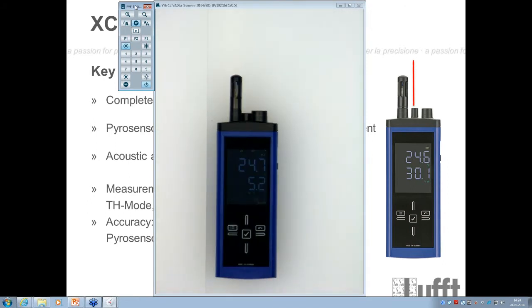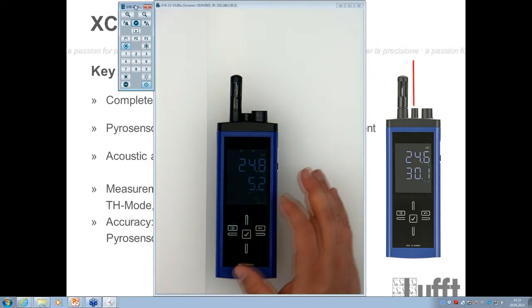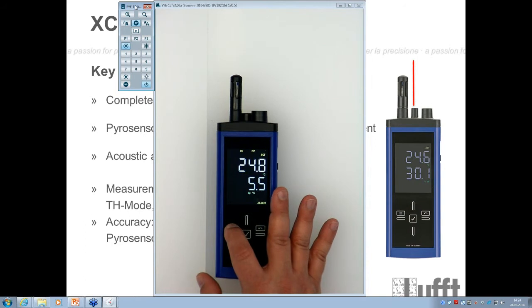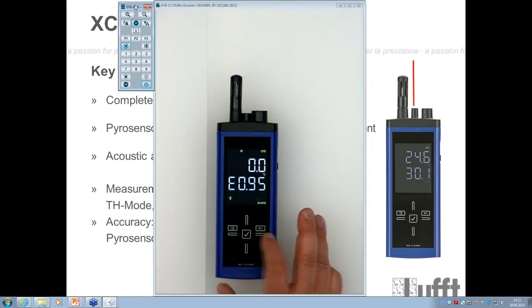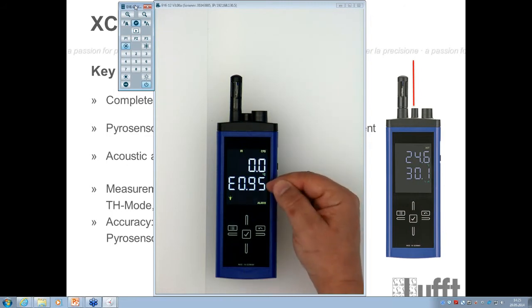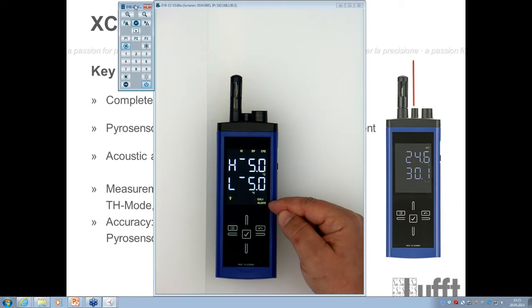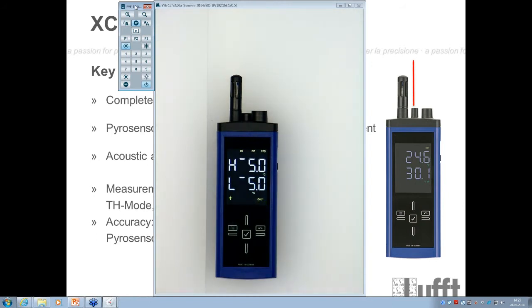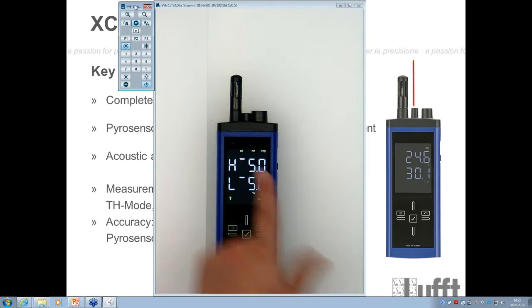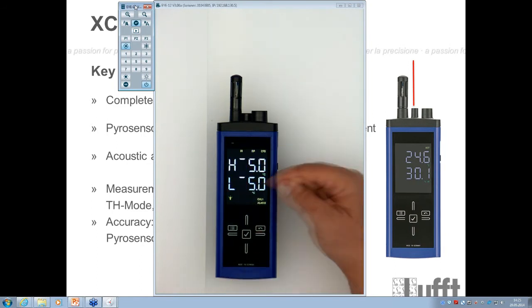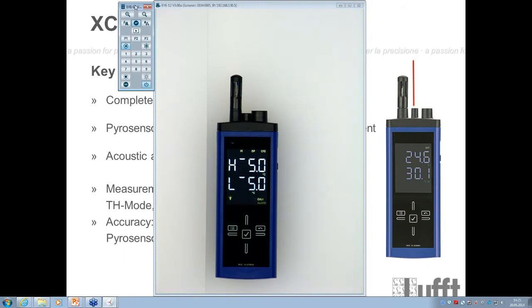If you want to change here now, of course I told you before that you have two thresholds, a high and a low threshold for the dew point to enter the alarm. Then you have to enter it into the configuration menu. You go to Cal 1, temperature offset, and emissivity value again, and the next step is, and now the alarm is blinking, that's the configuration menu for the alarm. It's a high threshold and a low threshold, which is configured for 5 degrees. Again, I will go back and show you. 5 degrees, 5 degrees. What does that mean? That means the alarm threshold is the sum of the dew point plus the high value and dew point minus the low value.